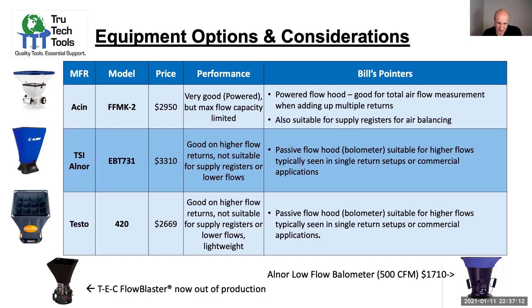The Testo 420 is a really nice unit, a little bit less money, and has a great temperature, humidity, pressure, and barometric pressure measuring device that you can snap out from it — the 420 manometer part — which can also be used for other applications. So it's a pretty good multifunctional device. There's also the Alnor low flow balometer, which goes up to 500 CFM — a similar limitation as the Flow Finder. It's not a powered hood; it's also a passive hood.